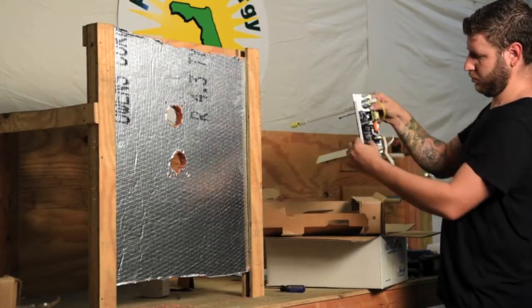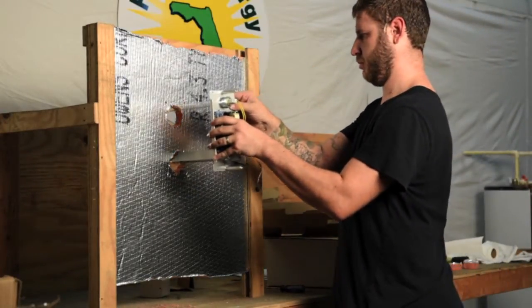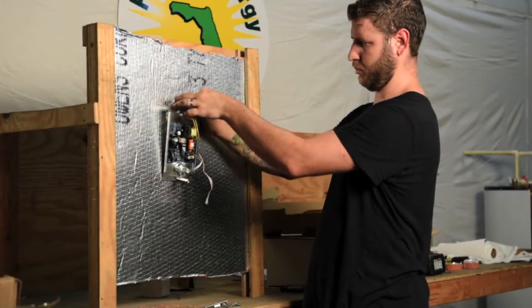Next, take the frame and insert into the duct board. Note that the bottom of the board has the electrical adapter. After inserting, thread your toggle bolts through the board and into the wing nuts, popping them through the duct board. Do not tighten them all the way down as they will each have to be tightened down little by little to make sure all corners are secured.